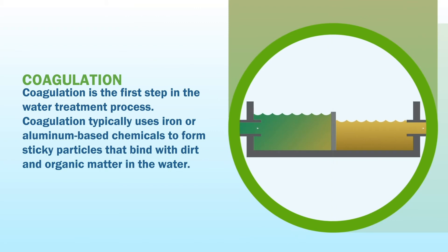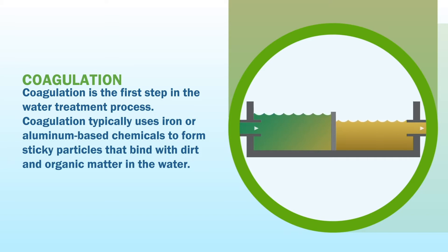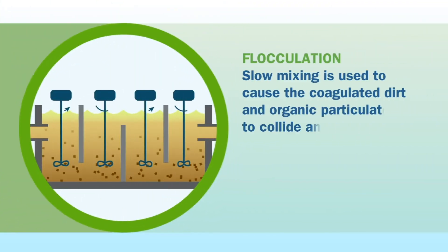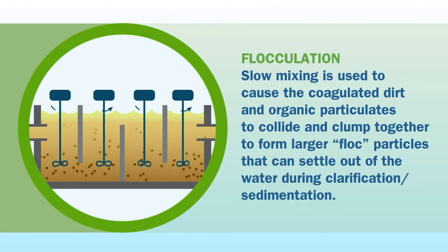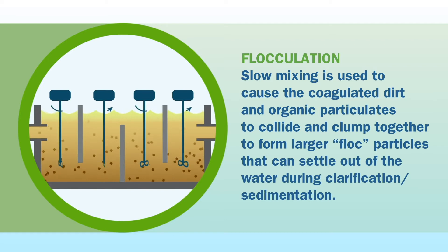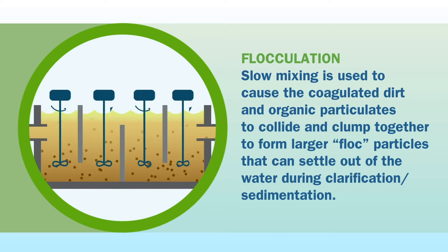Coagulation is the first step in the water treatment process. It typically uses iron or aluminum based chemicals to form sticky particles that bind with dirt and organic matter in the water. Slow mixing is then used to cause coagulated dirt and organic particulates to collide and clump together to form larger floc particles that can settle out of the water later in the process.